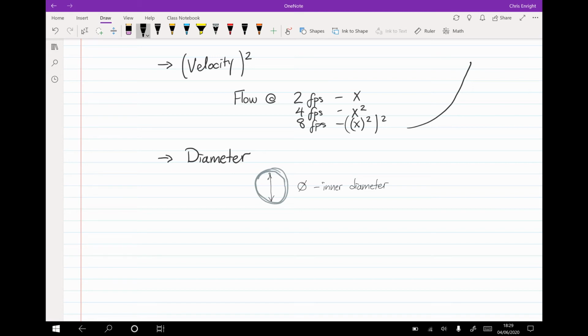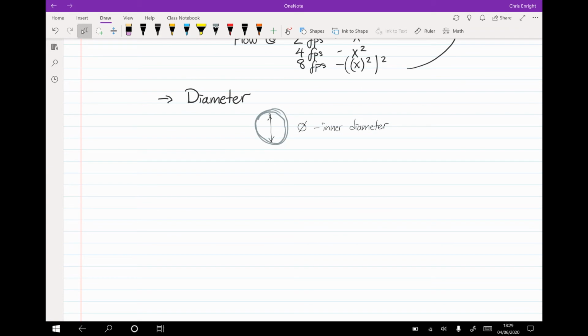So that's what matters the most. That dictates how much surface area is in contact with the water, and therefore how much friction we're actually going to see. So as we look at that a little bit more closely, a 1.75" hose, so 1.75" internal diameter, has about roughly half the friction as a 1.5".